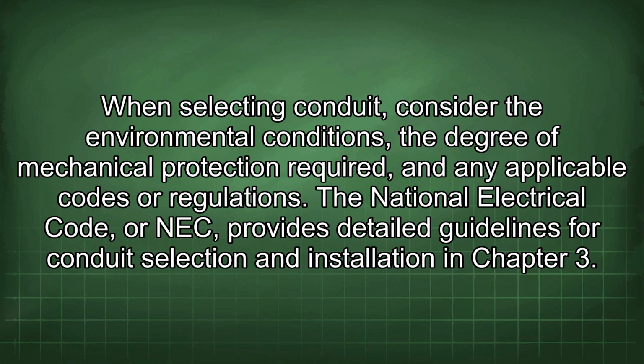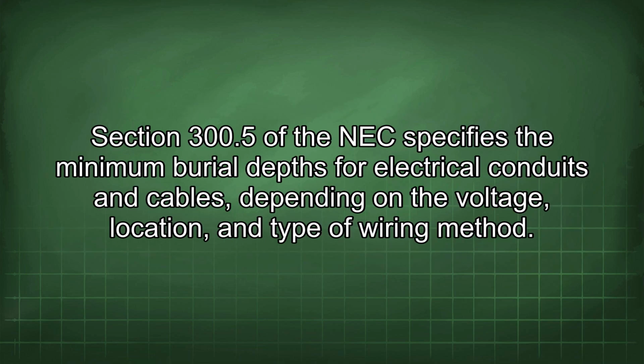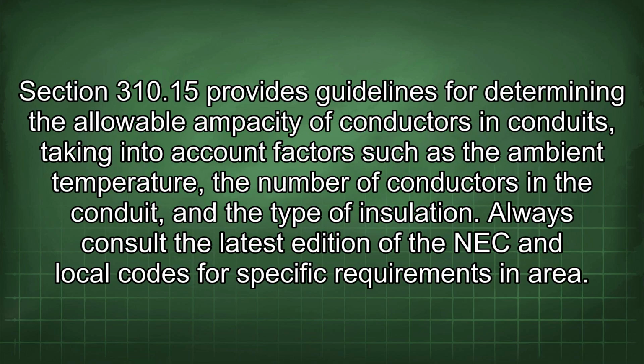The National Electrical Code, or NEC, provides detailed guidelines for conduit selection and installation in Chapter 3. Section 300.5 of the NEC specifies the minimum burial depths for electrical conduits and cables, depending on the voltage, location, and type of wiring method. Section 310.15 provides guidelines for determining the allowable ampacity of conductors in conduits, taking into account factors such as the ambient temperature, the number of conductors in the conduit, and the type of insulation. Always consult the latest edition of the NEC and local codes for specific requirements in your area.